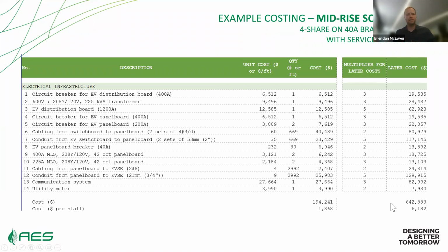We have found in practice that if we were to do this all at once, it typically is possible in existing buildings to do 100% EV ready retrofits at significantly lower cost points than this $6,000 per stall. It still will certainly be more expensive than doing this for new construction, but it is possible to do comprehensive retrofits. But for the way most buildings have done this to date, sort of one-off implementations of a couple of EV charging parking spaces, it's kind of a reasonable ballpark value that can demonstrate the importance of future-proofing this parking.